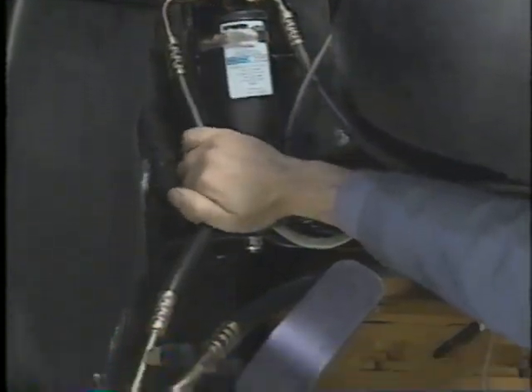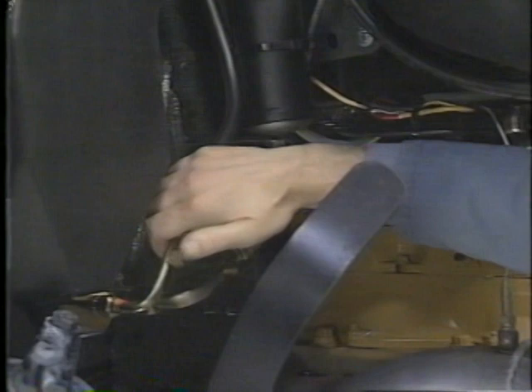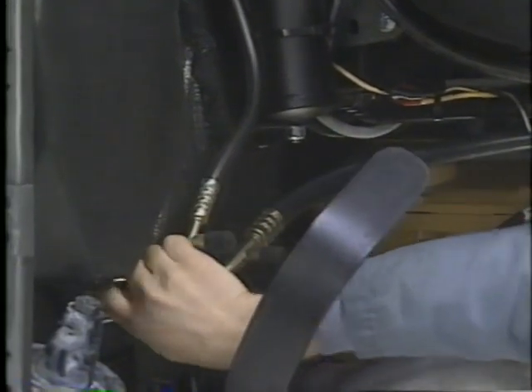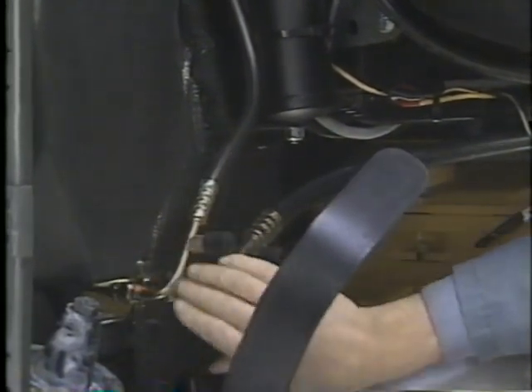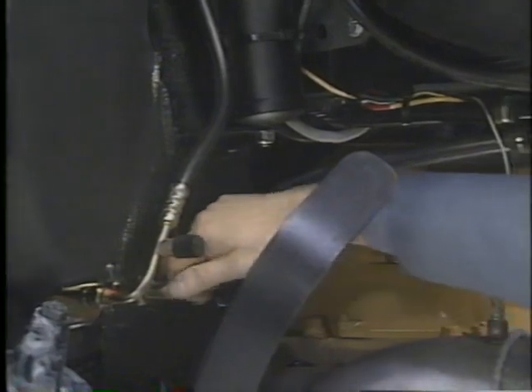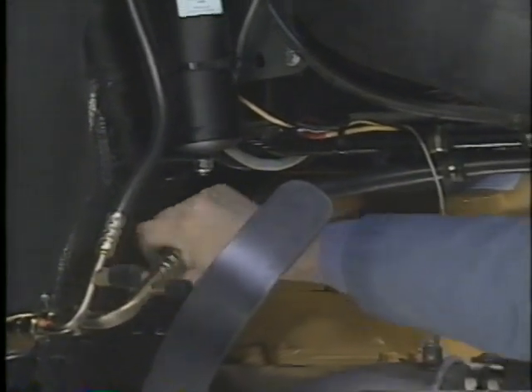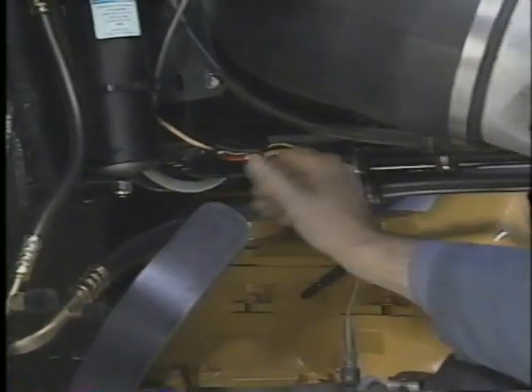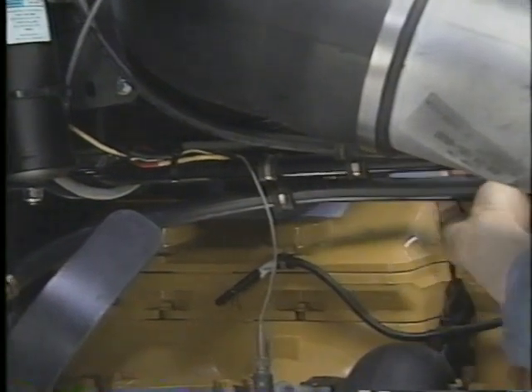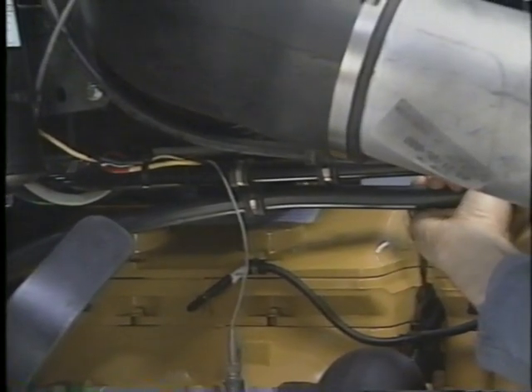The line from the receiver dryer to the evaporator should feel warm. An icy spot indicates a restriction. Finally, the line from the evaporator to the compressor should feel cold. A warm line could indicate a bad expansion valve. An icy line indicates that the expansion valve could be stuck open or that the system has been overcharged with refrigerant.